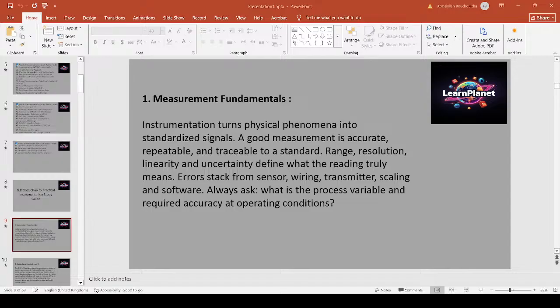So, the measurement is the bridge between reality and control, converting a temperature, pressure, level or flow into a standardized electrical or digital value that people and control systems can act on. A useful measurement has known accuracy, repeatability: can you get the same result repeatedly under the same conditions? And traceability: calibrated against a standard with a certificate.